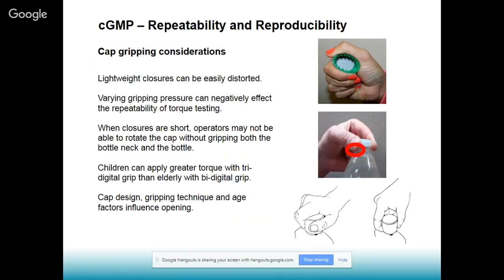Here, I just wanted to give you an idea about the problem with the manual torque testing process. So the cap gripping is definitely a variable if you have manual operators, and varying cap gripping pressure can introduce error in the torque testing. And in the middle, you see a picture of a narrow cap, which is probably not happening in the pharmaceutical industry, although some creams may require FDA control and have a very narrow or short cap design. In those cases, the problem is how do you grip and grab the cap without touching the container. So that's just another reason why we want to automate these tasks.